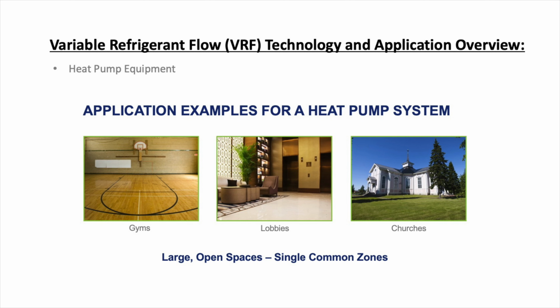Good applications for a heat pump. Basically any large open space that has single common zones is a good candidate for a heat pump system. So for example, you have gyms, hotel lobbies, churches, large common office spaces where they will all be in the same heating profile or cooling profile. Those would be good candidates for a heat pump system.